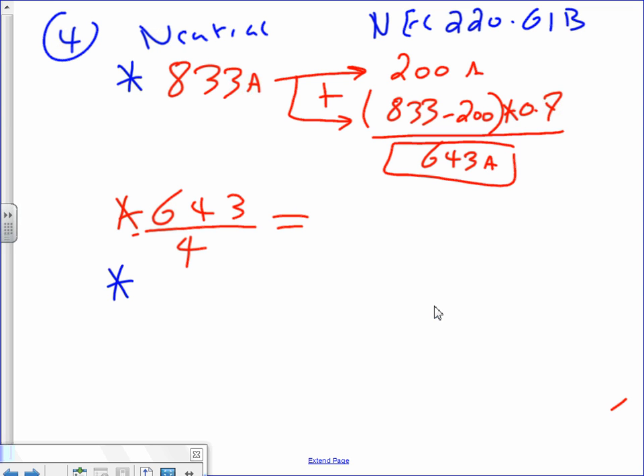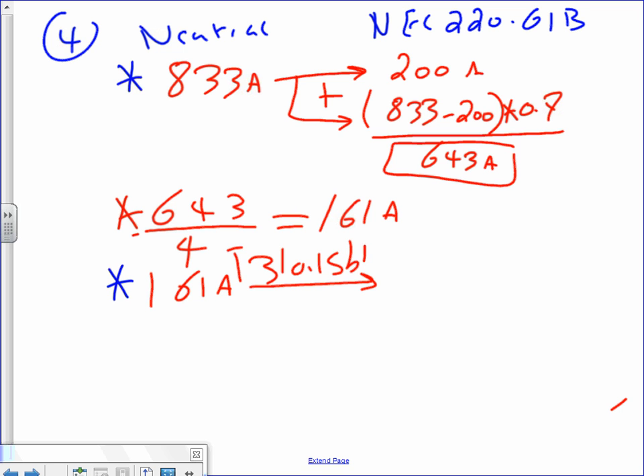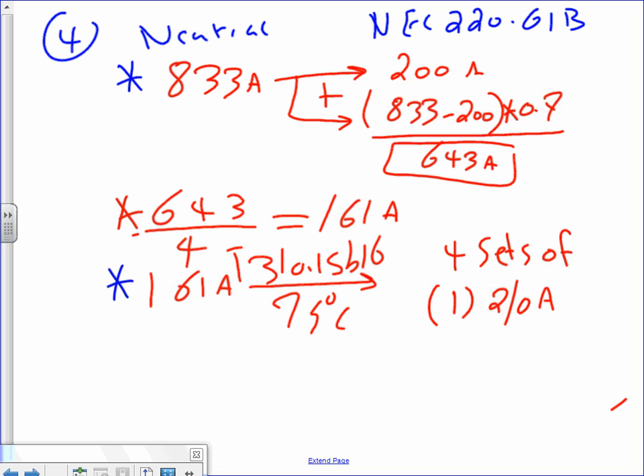Here you don't pull a ground because you're coming from the service. But yeah, if it's a feeder, you'll have a ground within each one of them, in each conduit, if needed, if you're using PVC. Now, if you're using EMT, you don't need to pull a neutral. Yeah, a ground. Okay, so if you guys do the math on this one, 161 amps, okay? And then you take the 161 amps, now we size to Table 310.15 B16 under the 75 degree column, and that will give you the following: 4 sets of 1 conductor, each one of them 2/0 AWG THHW.